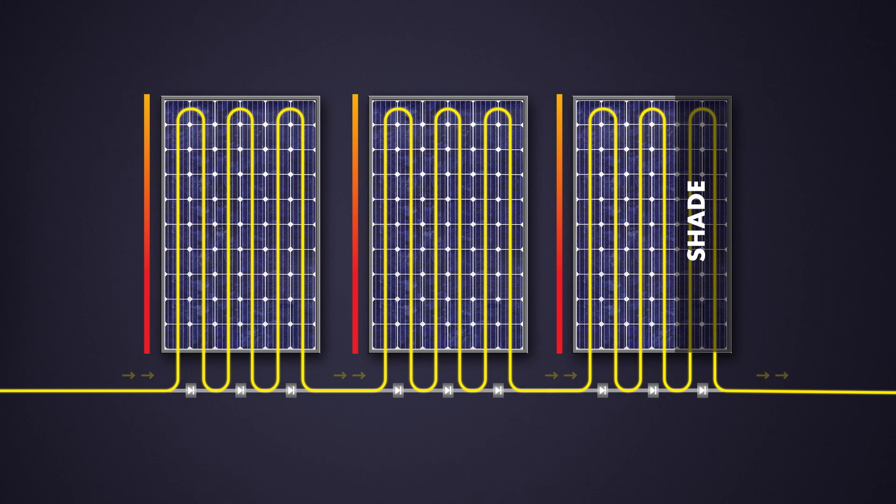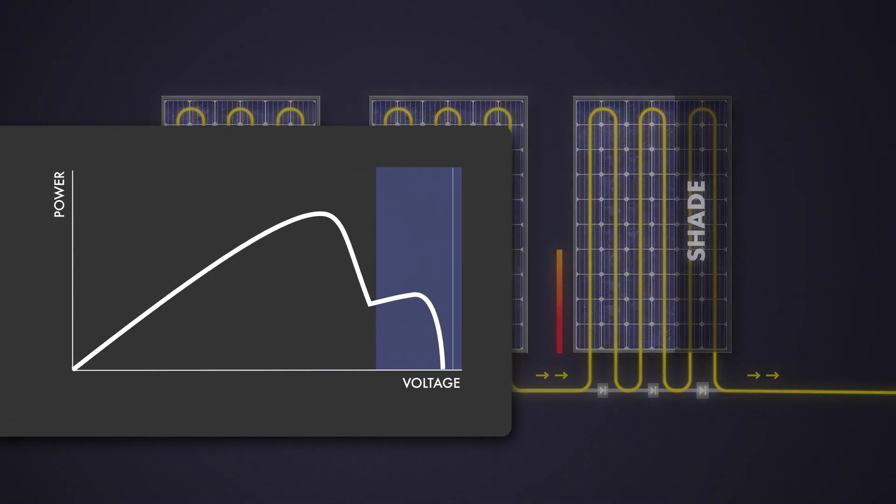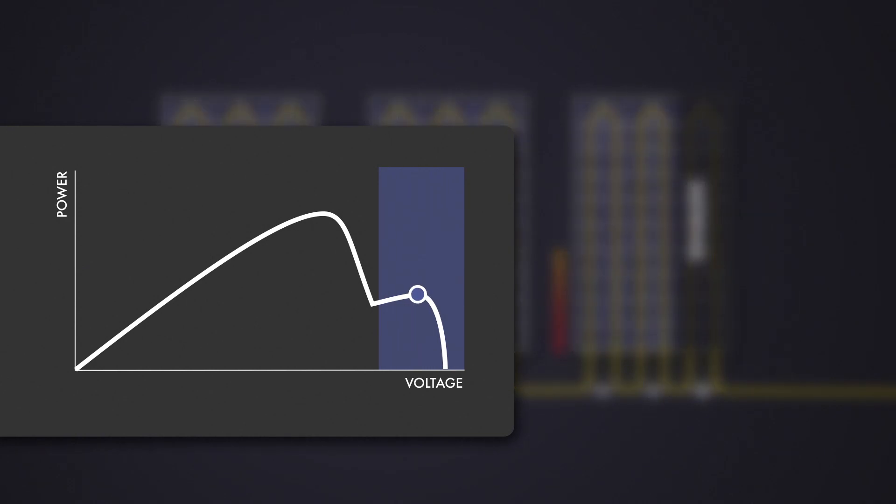In case of a partially shaded PV array when using classic MPP tracking, the current through all PV modules will be limited to the current of the shaded PV module. Due to its classic MPP tracking algorithm, the inverter chose the wrong MPP voltage at a low local maximum powerpoint. The bypass diodes are not active.